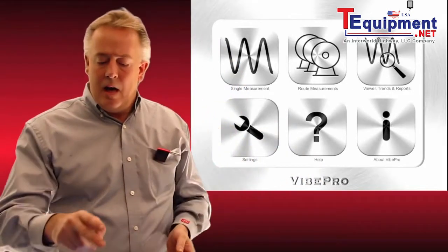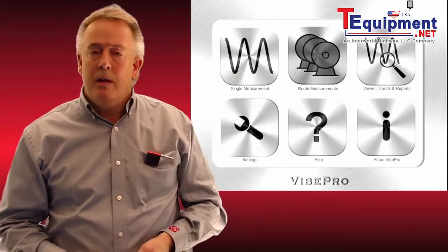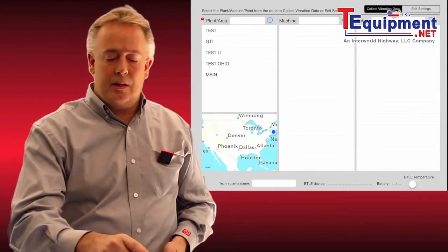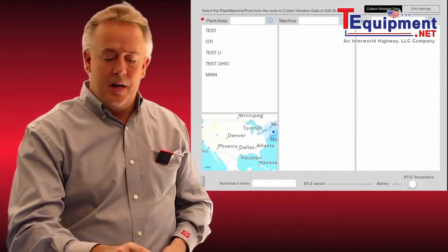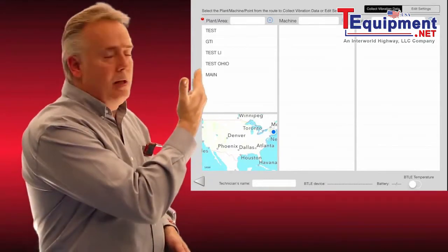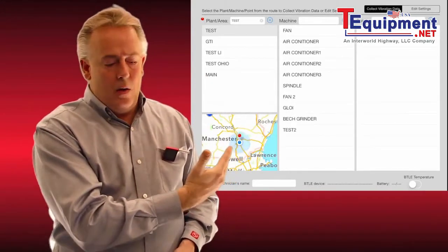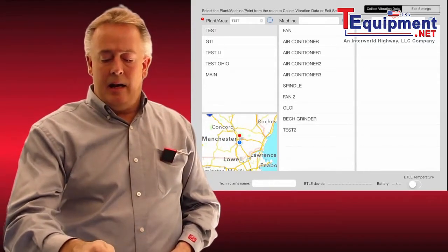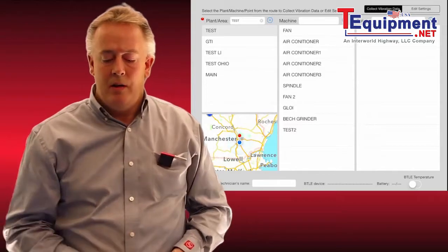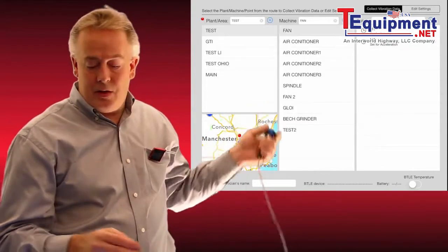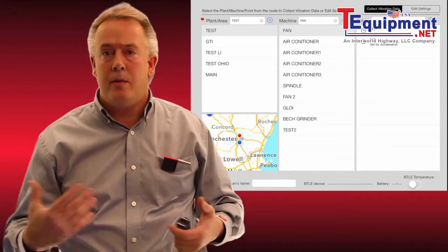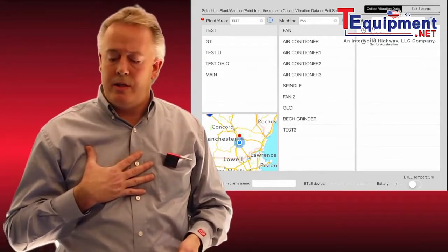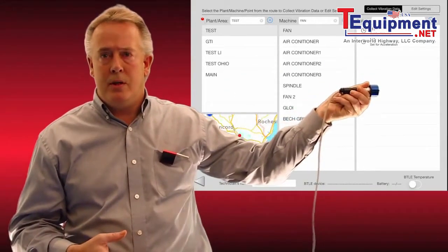I have an accelerometer right here next to me. I'm going to open the route measurement mode and you can see I have a hierarchy behind me of test GTI — those are our plants and areas. I'll hit the first button which immediately releases all of the asset points or equipment that I have at that test area of the plant. I'll pick the first one, which is a fan, and you'll see it pops up with my two measurement points that I've already pre-programmed — H1 means horizontal one.